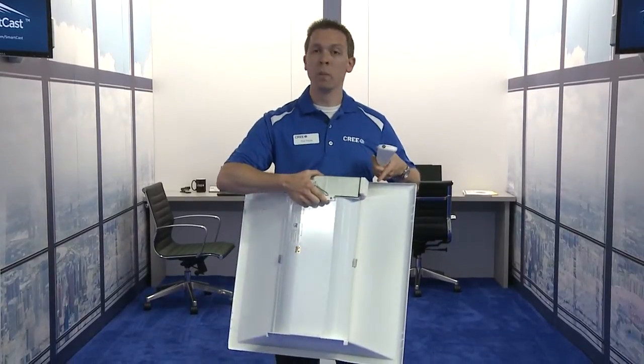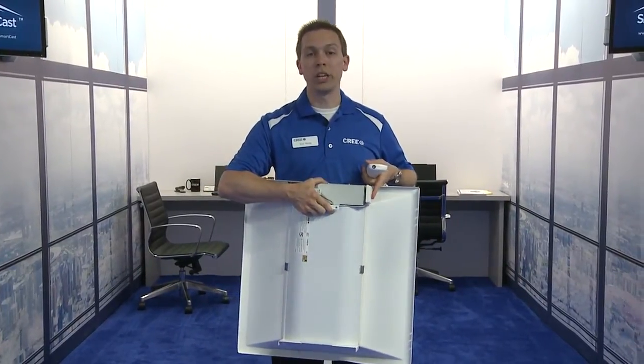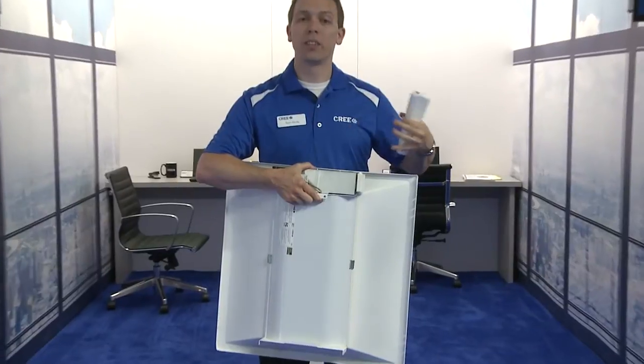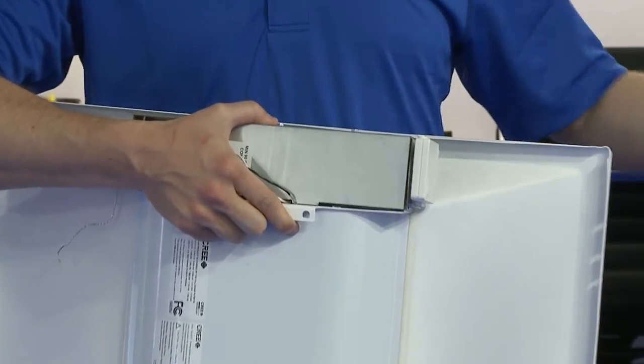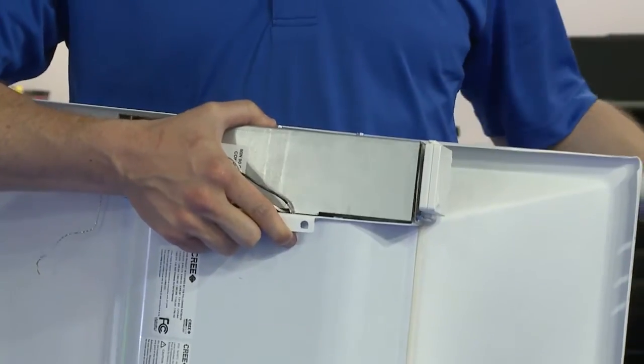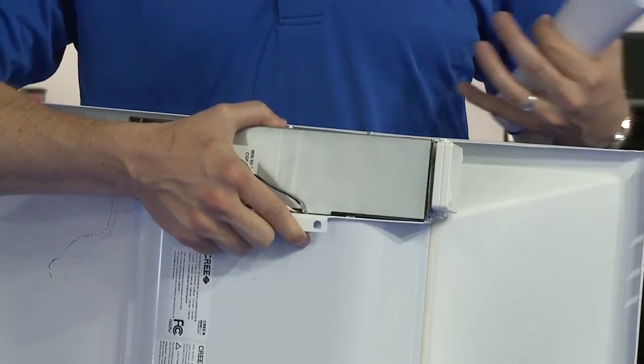The next thing we did was install wireless communication directly into the fixture. This enables fixtures to talk to fixtures and fixtures to talk to dimmers, eliminating the need for control wires and greatly reducing the amount of equipment that we need to install on a project.